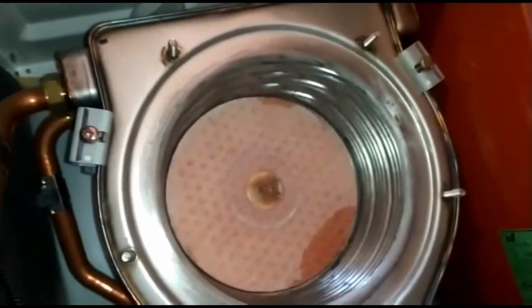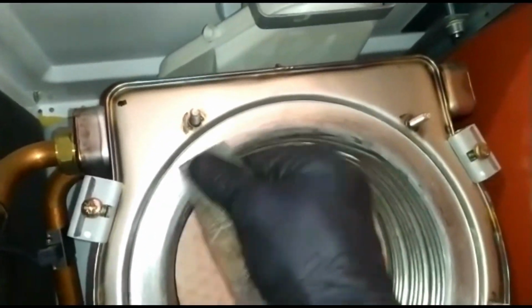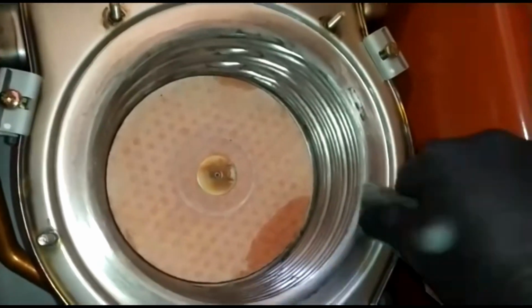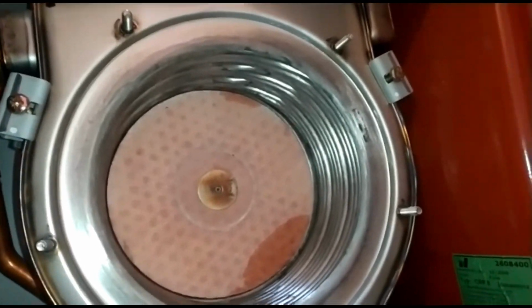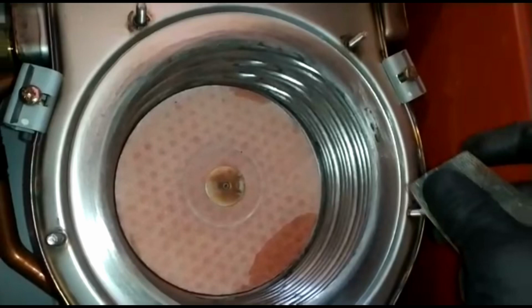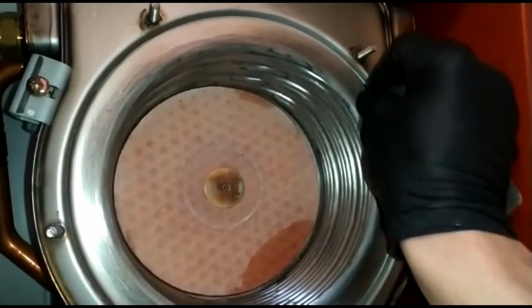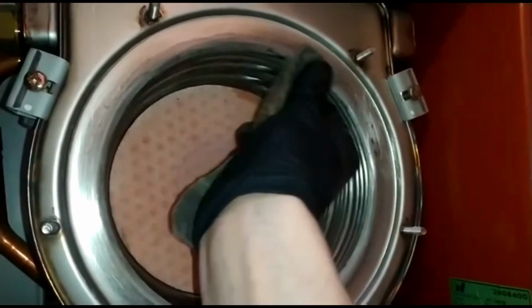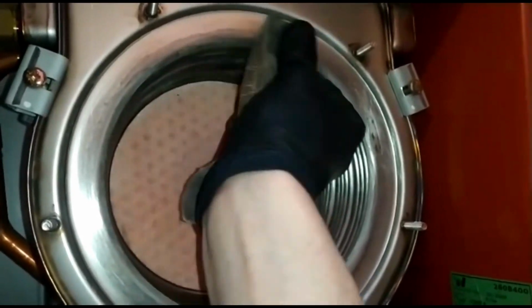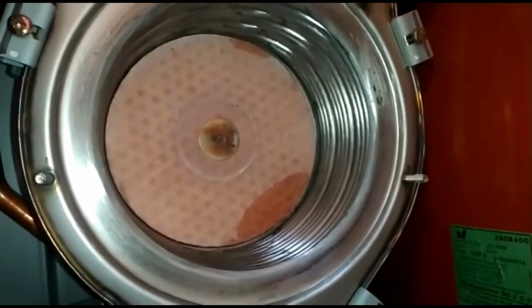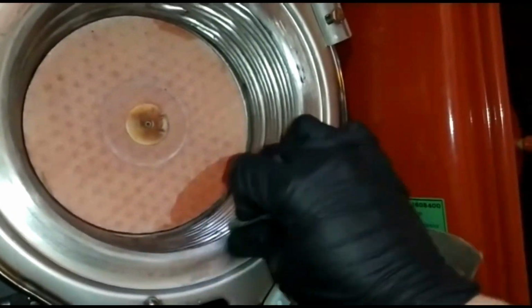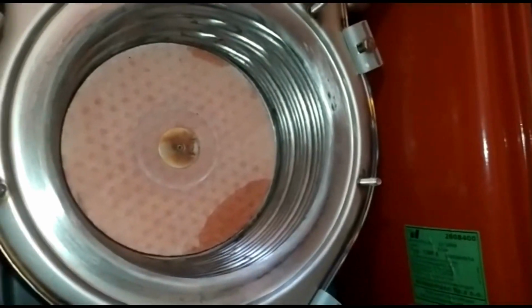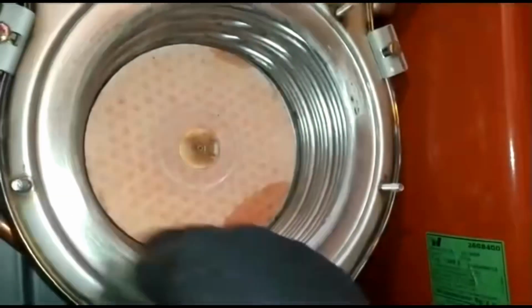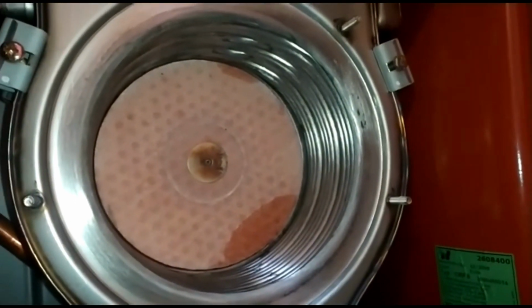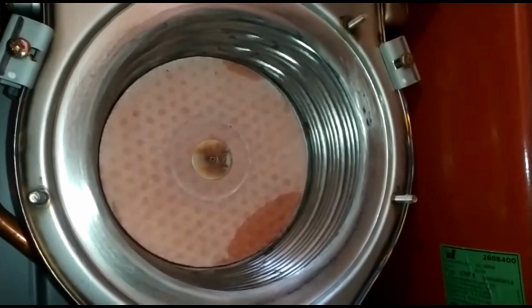One other thing I do is clean around the edges here. It doesn't say you have to in the instruction booklet, this is just something I do. I clean off all the old scum of the old G10 seal, because normally if you've got a graphite one coming off it leaves a bit of scum, a few high points on the edge. So I clean it all down so that when the new G10 graphite seal gets crushed against that, it's got its best chance of sealing properly.